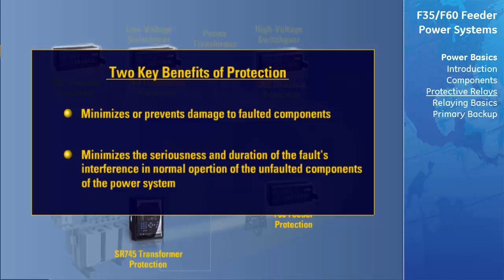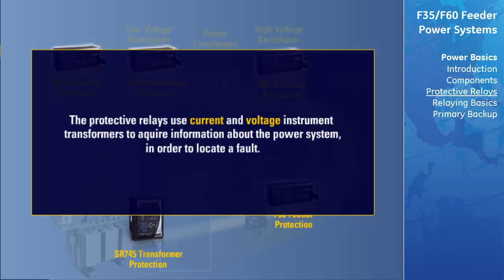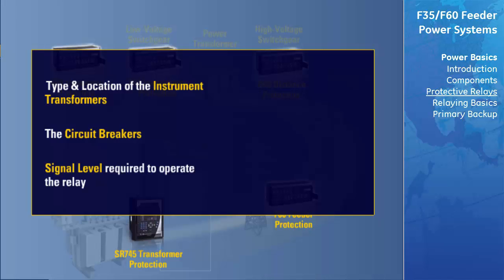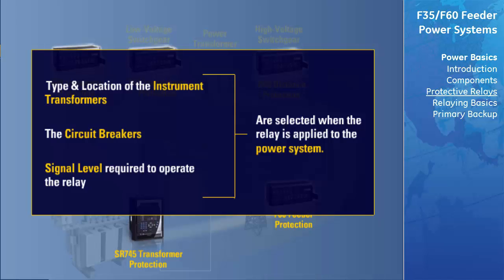The second benefit is that the quick response minimizes the seriousness and duration of the fault's interference with normal operation of the unfaulted parts of the system, allowing them to continue to supply their normal power. In many cases, the unfaulted parts of the power system can supply the additional power to replace what was normally supplied through the faulted component. The protective relay uses current and voltage instrument transformers to acquire information about the system such that a fault can be located.